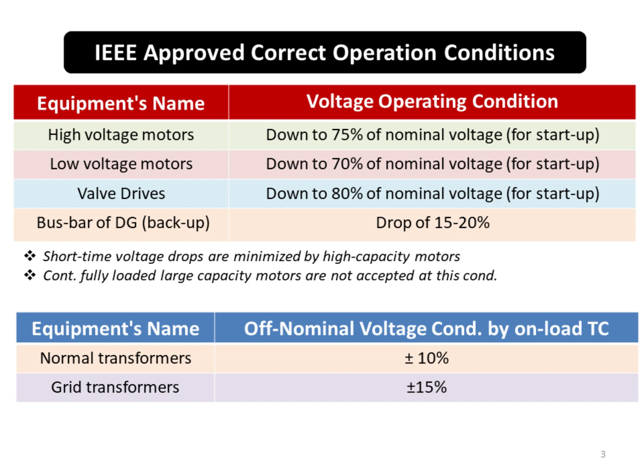IEEE standards define safe operating voltage ranges for NPP equipment. For example, high-voltage motors can operate down to 75% of nominal voltage during startup, while low-voltage motors can go to 70%. Valve drives require at least 80%. Backup diesel generators can tolerate 15 to 20% voltage drops. Note, continuous operation at these levels is not acceptable. Transformer tap changers can compensate for off-nominal voltages within plus or minus 10 to 15%.